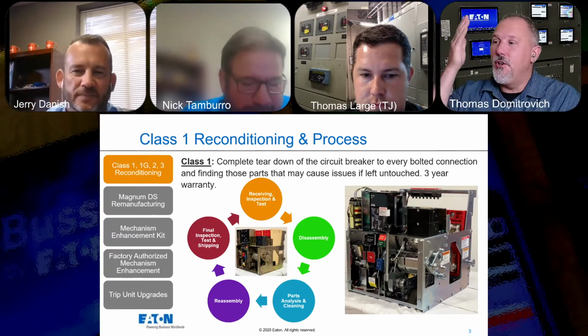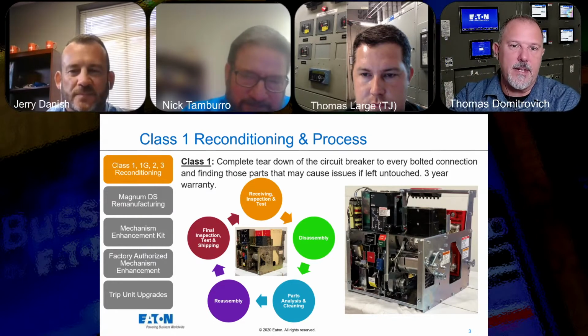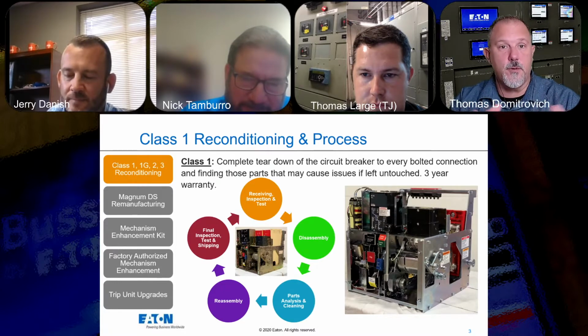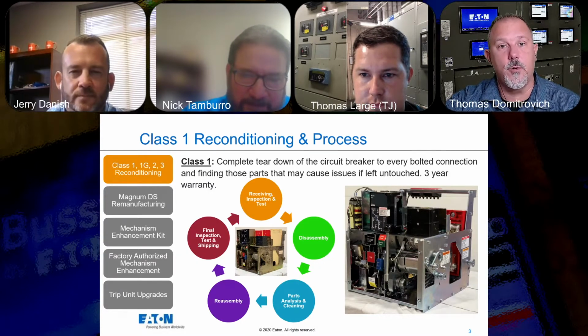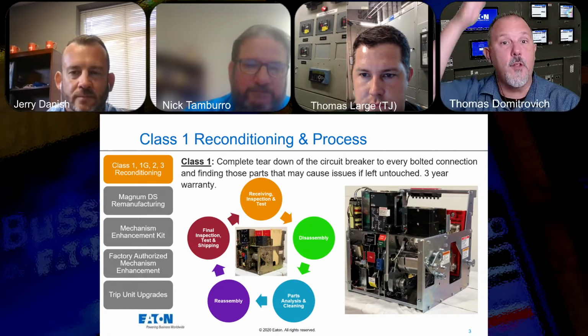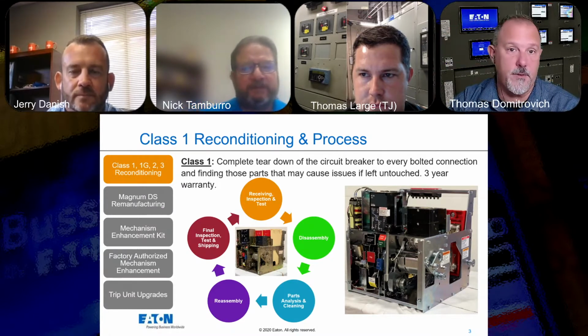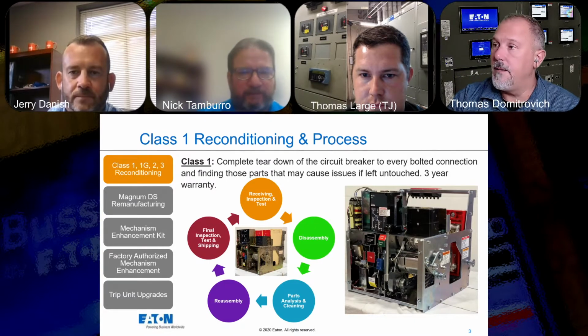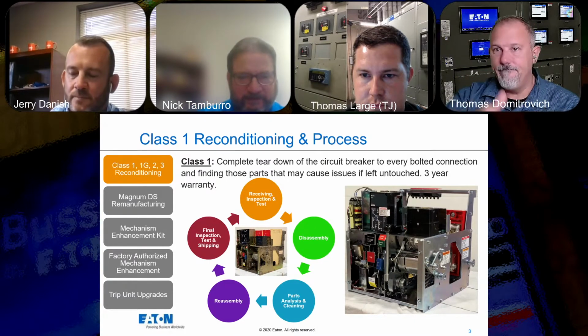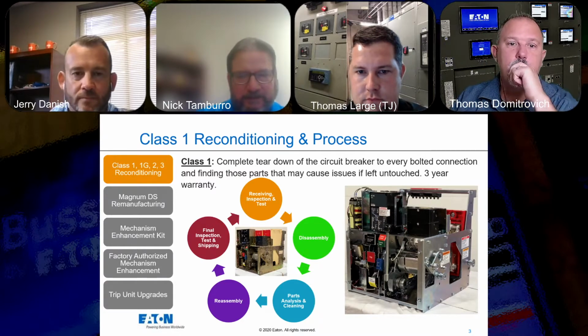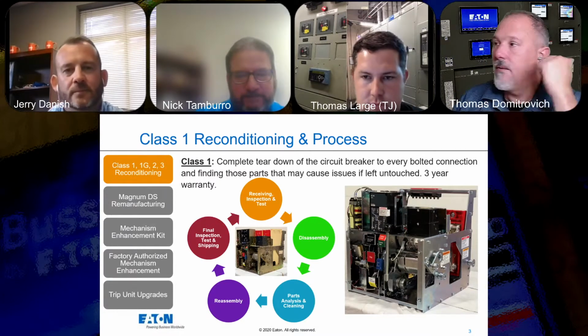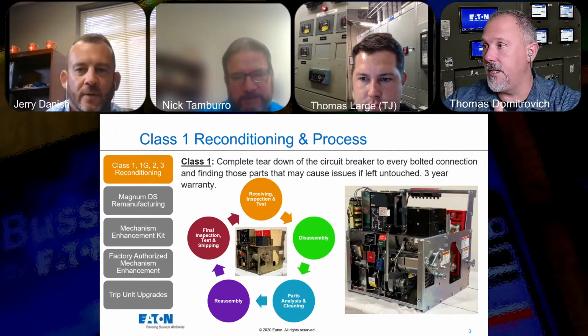So you're testing the CTs, the mechanisms, and the trip curves, and to your point, making sure the trip curves align with the way they came in, whatever those settings were. But somebody would still want to look at their selective coordination study to make sure it's set appropriately when it's installed, for the long time pickups, long time delays, and all that good stuff, right? Correct. That's where our PSE group comes in, Power Systems Engineering. Yeah, absolutely.